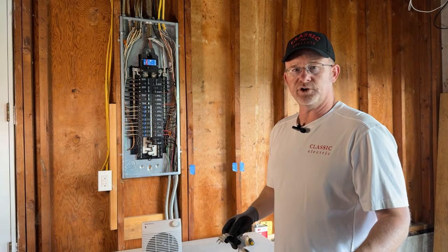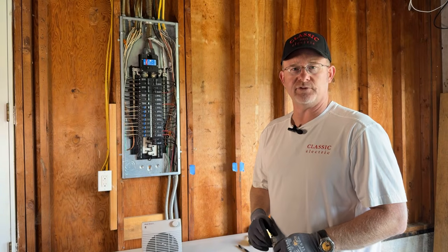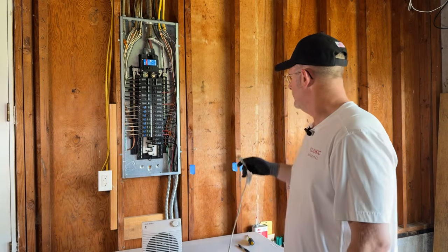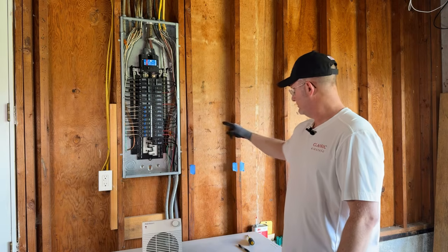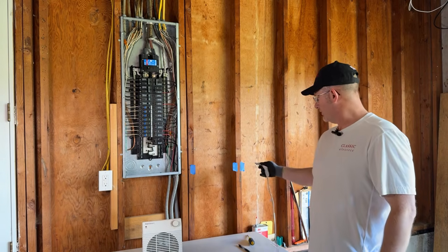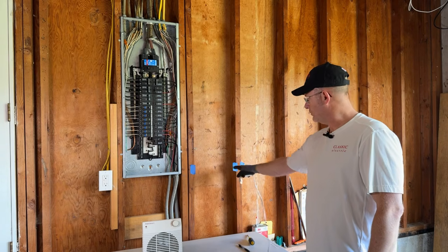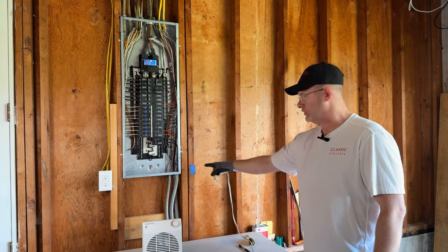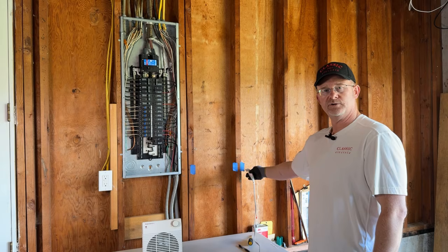So you get this fallacy over the years that if I don't have anything plugged into an outlet, it won't cause a fire. Oh, yes, it will. And I'm going to explain to you why. The power comes out of the electrical panel to the first stop, to the second stop, to the third stop. If you take this heater and you plug it in to the third stop, and you have a loose connection here, or you have a loose connection here, you will have a fire here or here while this is plugged in right here.